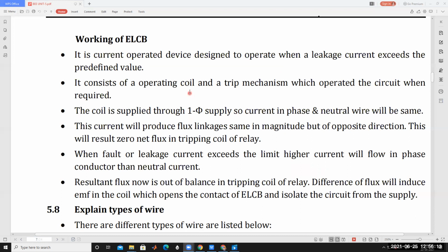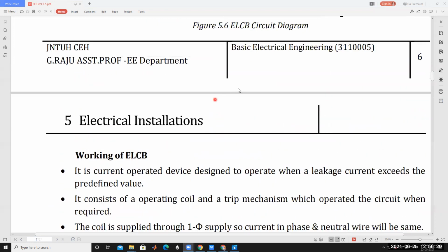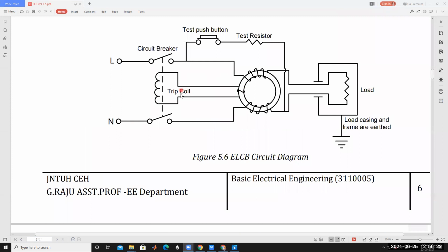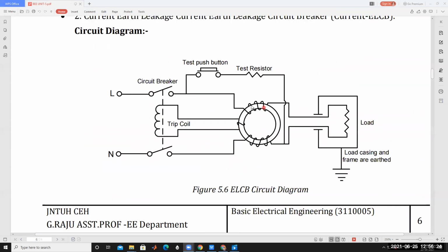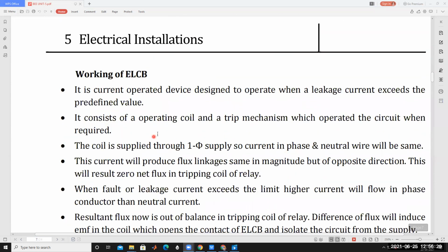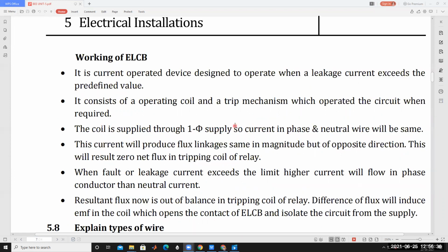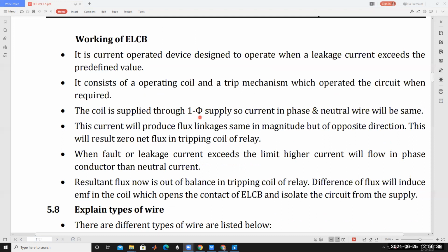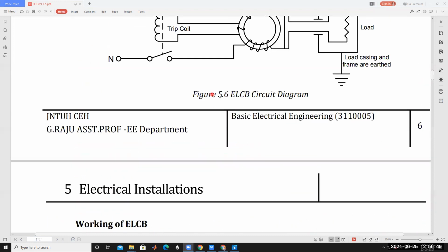It consists of an operating coil and a trip mechanism, which operates the circuit when required. This is called the trip coil, and this is called the operating coil. The coil is supplied through a single phase supply, so the current in the phase and neutral wires will be the same.